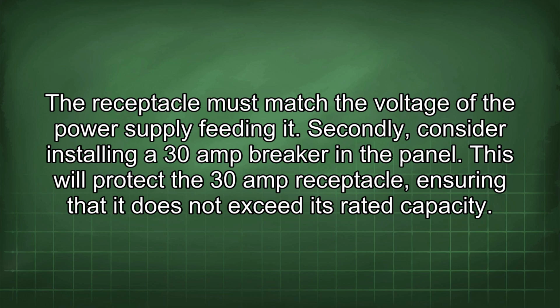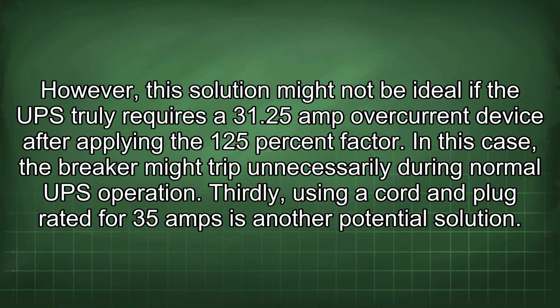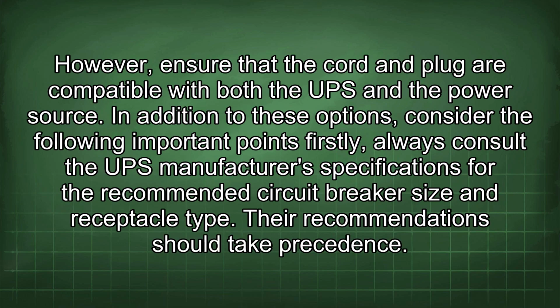Secondly, consider installing a 30 amp breaker in the panel. This will protect the 30 amp receptacle, ensuring that it does not exceed its rated capacity. However, this solution might not be ideal if the UPS truly requires a 31.25 amp overcurrent device after applying the 125% factor. In this case, the breaker might trip unnecessarily during normal UPS operation. Thirdly, using a cord and plug rated for 35 amps is another potential solution. However, ensure that the cord and plug are compatible with both the UPS and the power source.